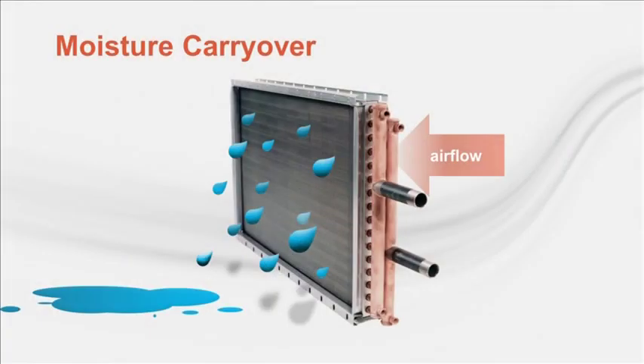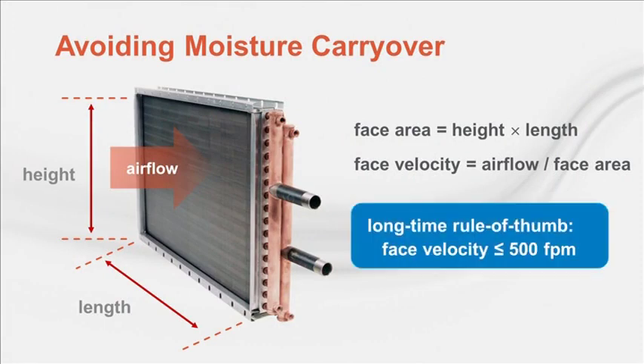In most applications, the cooling coil also dehumidifies as water vapor in the air condenses on the cold fin surfaces. The water drains down the coil surface, drops into the drain pan, and is piped away by the condensate drain line. When a coil dehumidifies, it must be selected to prevent moisture carryover. Too high a face velocity through a wet coil can result in condensed water being blown off the fin surfaces onto downstream components. A long-time industry rule of thumb for avoiding moisture carryover has been to select cooling coils for face velocity no greater than 500 feet per minute at design airflow.